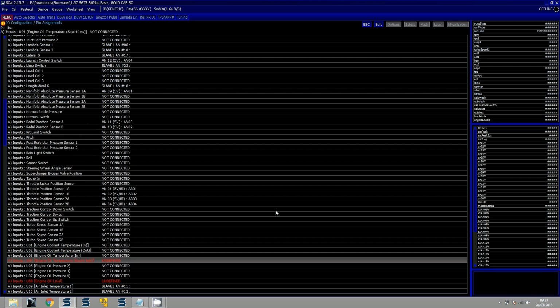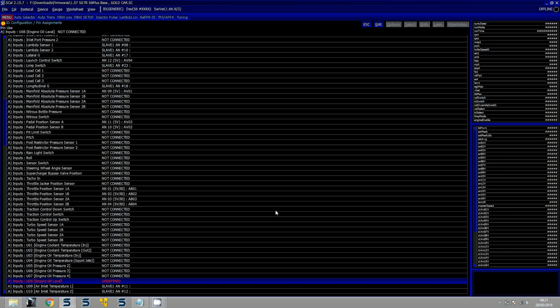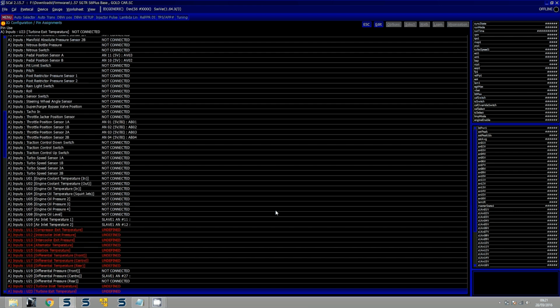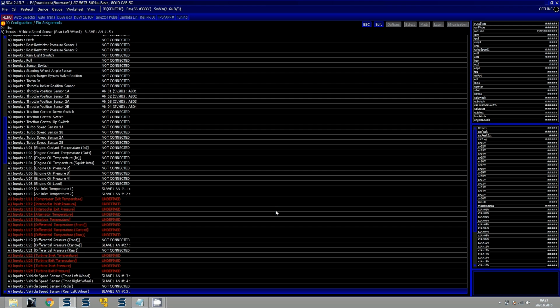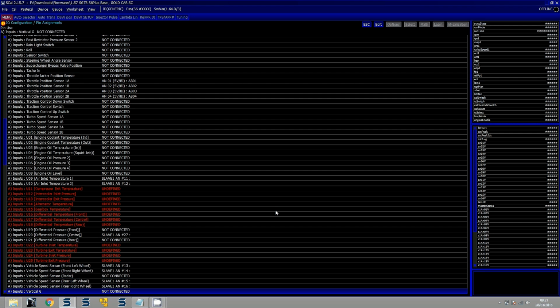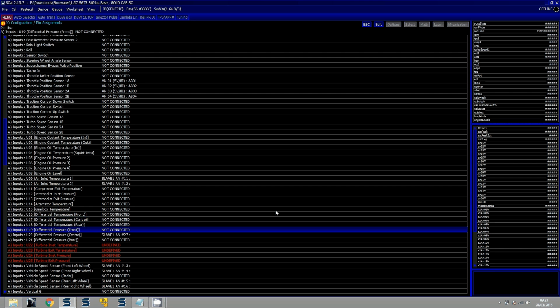There's a few extra inputs down here for engine oil level and similar, and you'll notice these inputs are now segregated at the bottom into their own sensor definitions starting with U. The important reason for this is that these sensors can now be renamed - these are user definable sensor inputs not used by any strategy, so it's important, as they could potentially damage something if we start changing them incorrectly. We have to unassign these, and we'll go back over them afterwards to talk about how to rename and use them.